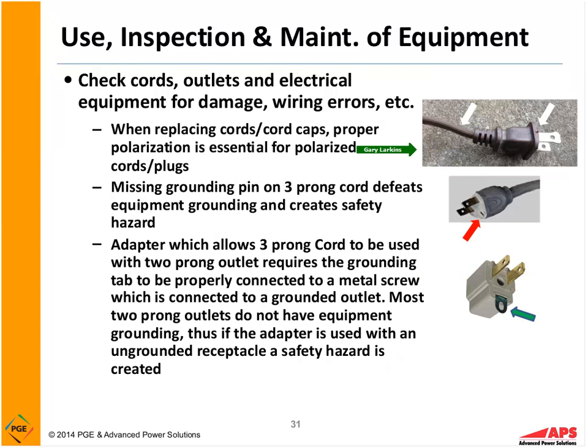The equipment should have been designed to work with this cord, be UL listed for it or ETL tested to the UL standards, but it's important that we don't use 2-wire cords on devices that need a 3-wire cord. And it's also important that we make sure that, in this case, we have a ground pin missing. It's a hazard. Or here we have an adapter. Some of the older homes do not have ground wires, and people sometimes apply the adapter, but if they do not bend this tab down and connect it to a screw that's connected to a grounded outlet, this is a safety hazard. Even though you connected it to the screw, you have to test and make sure this is connected to a grounded outlet. So again, it's very important that we follow safe work practices in the use of cords.